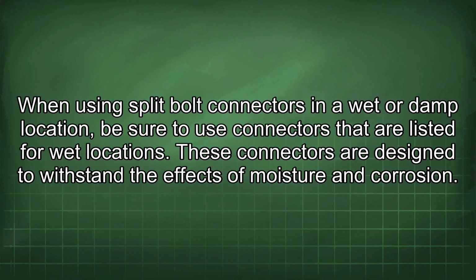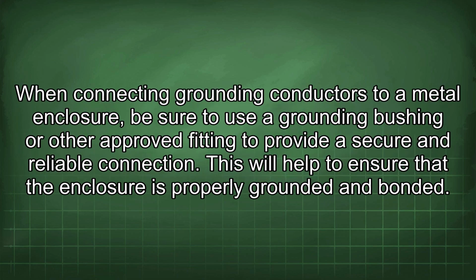When using split bolt connectors in a wet or damp location, be sure to use connectors that are listed for wet locations. These connectors are designed to withstand the effects of moisture and corrosion. When connecting grounding conductors to a metal enclosure, be sure to use a grounding bushing or other approved fitting to provide a secure and reliable connection. This will help to ensure that the enclosure is properly grounded and bonded.